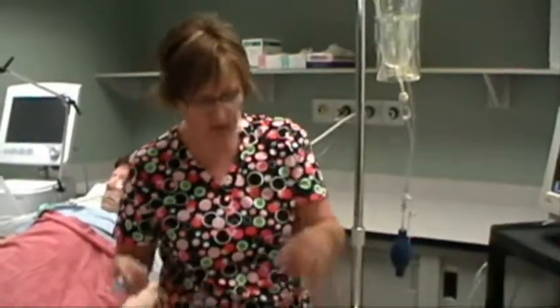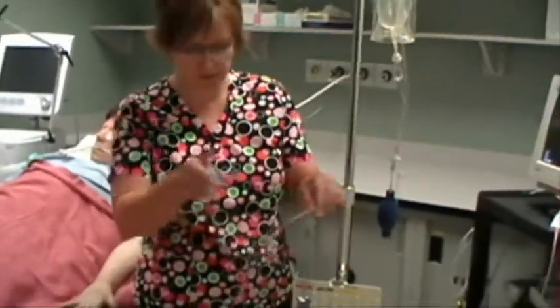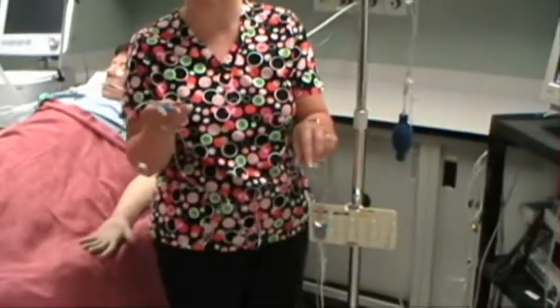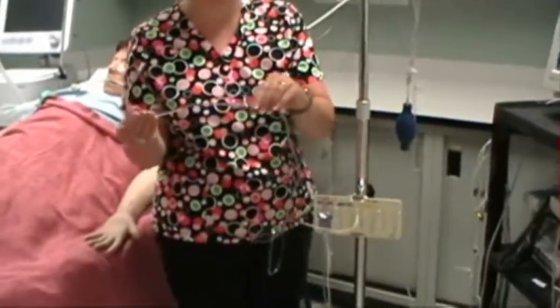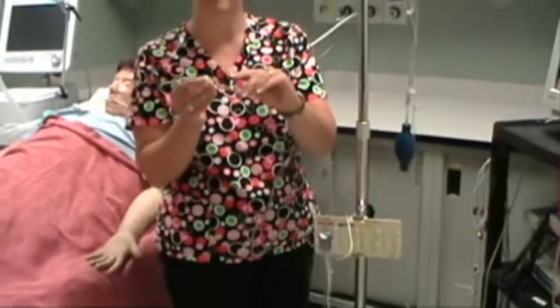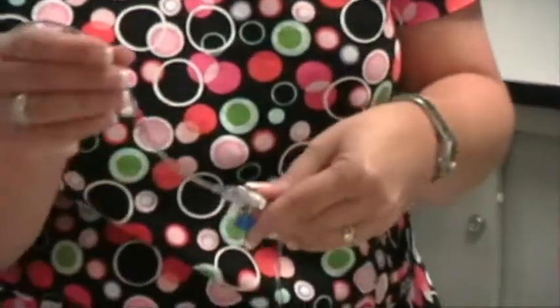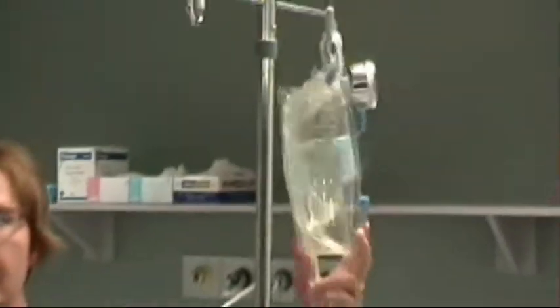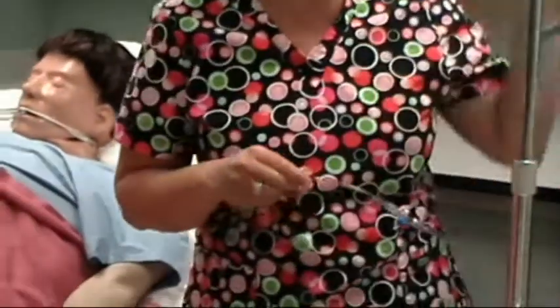Alright, so now we have our fully set up transducing system. So we've flushed the whole line, we've made sure that there's no air in the line, and we've made sure that all our stopcocks are in the off position. Okay. We've also added the label so that we know that this is an arterial line, and we've got a pressure bag inflated to 300 millimeters of mercury. So this has been leveled with the phlebostatic axis on the patient, and we have zeroed the system.